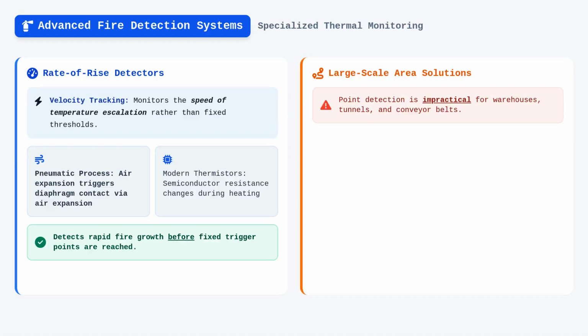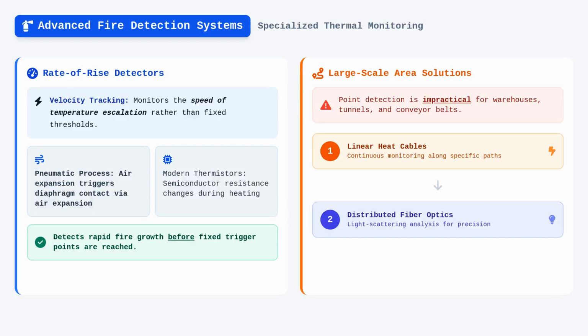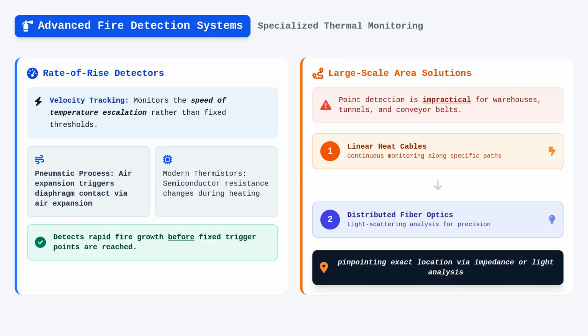When designing for expansive areas like warehouse logistics, conveyor belts, or subway tunnels, point detection becomes impractical. In these scenarios, linear heat detection cables or distributed temperature sensing utilizing fiber optics are employed. These technologies provide continuous monitoring along specific paths, allowing the fire alarm control unit to pinpoint the location of the heated section based on electrical impedance or calibrated light scattering analysis.